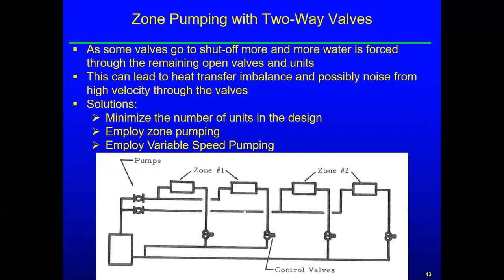We can only have a minimum number of units in the design, but you have to design for the whole building, whatever it is. So that may not be real practical. We can employ zone pumping, which this picture below shows that we've got zone one and zone two. So instead of having four units on one pump, you've got two units on one pump and two units on another pump, which I guess will help some. Or today we would probably employ variable speed pumping, which then you would set a particular pressure difference between the supply and the return mains, and simply the pump would modulate speed to maintain that, which is a big benefit and a big improvement. So these days, that's the direction you would want to go with this.